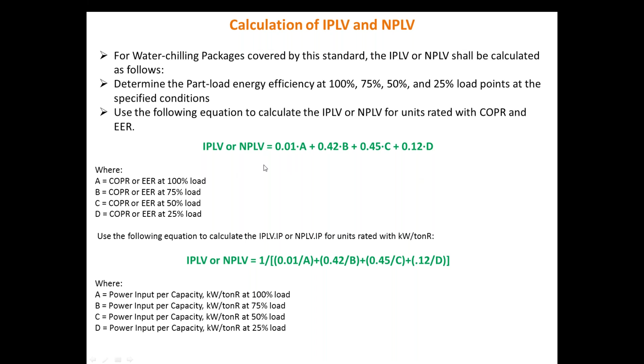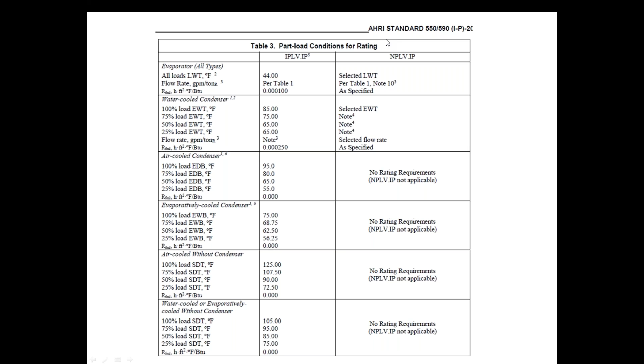This part load performance at IPLV and NPLV, as I already told you, is calculated based on AHRI standard 550, 590, for various chillers - that is, evaporator based, water cool condenser, air cool condenser, evaporatively cool condenser. Based on the types, IPLV is standard and NPLV is non-standard. Of course, no standard mentioned in the IPLV is followed when calculating the NPLV. The detailed standard you can obtain from the AHRI website, where you will see the detailed procedure of how to conduct the IPLV test with standard 550, 590.